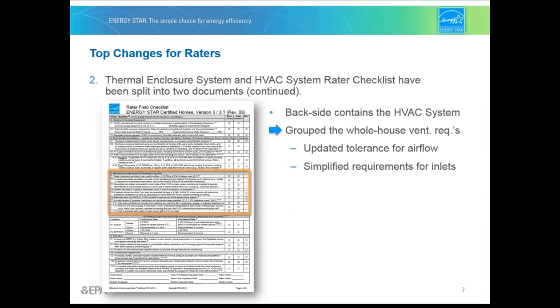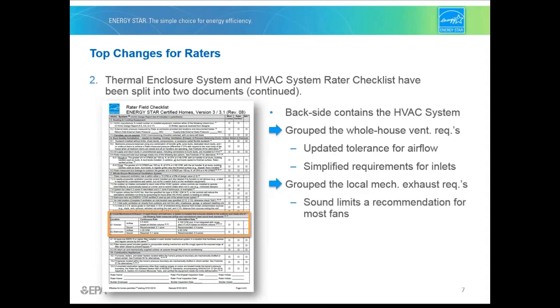We've grouped all of the whole house ventilation requirements into one section, updated the tolerances for airflow measurement, and simplified the requirements for air inlets. We've also grouped all the local mechanical exhaust requirements into one section, and have made the sound limits a recommendation rather than a requirement for most fans.